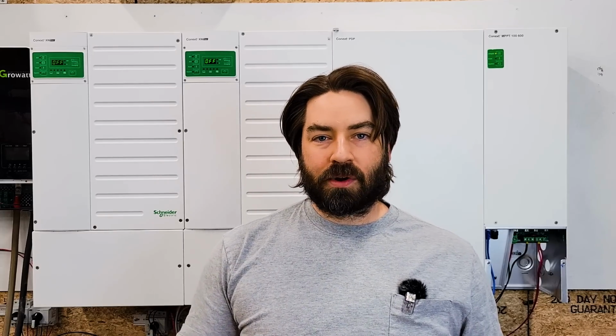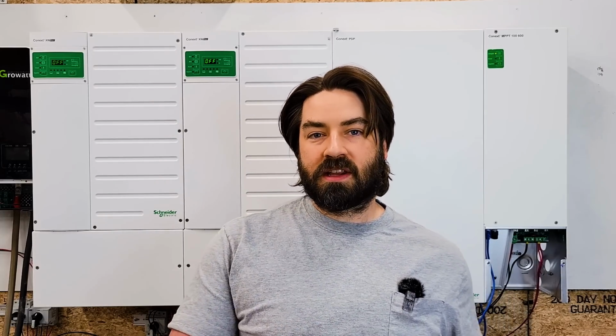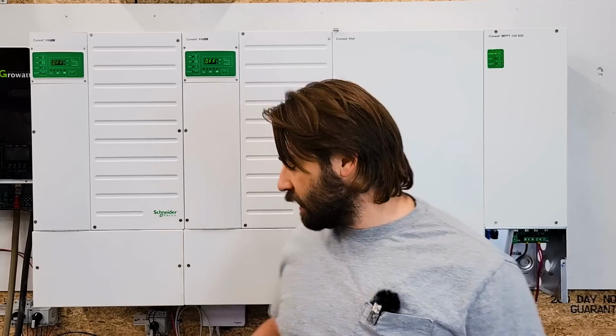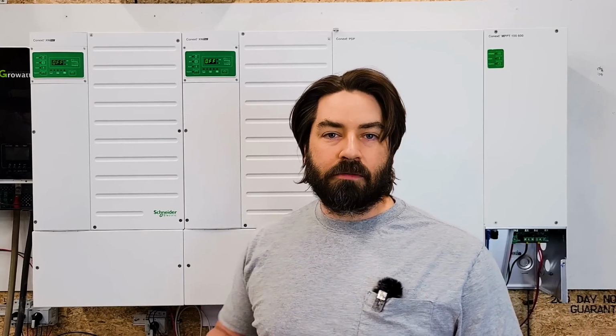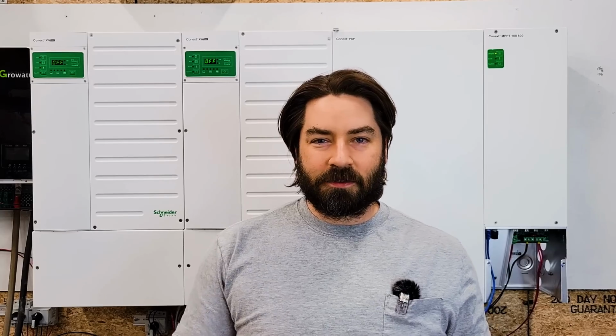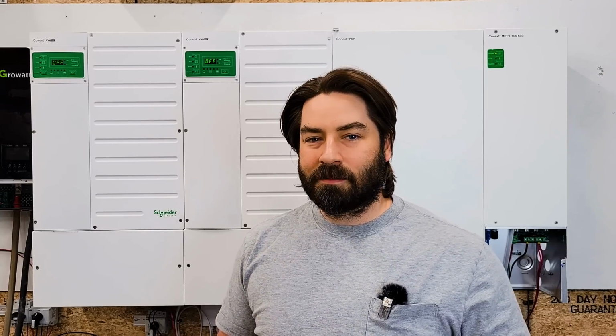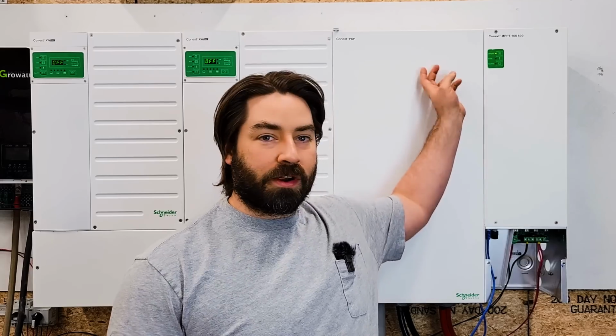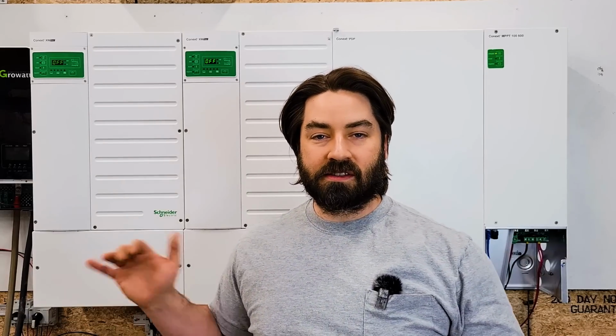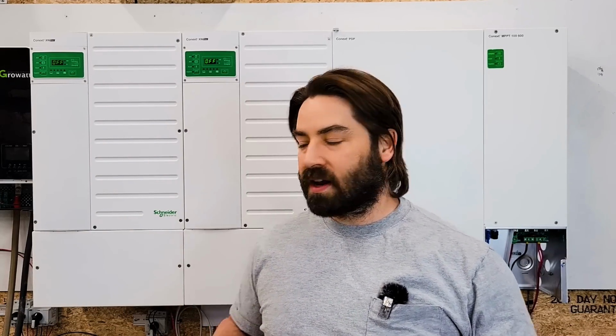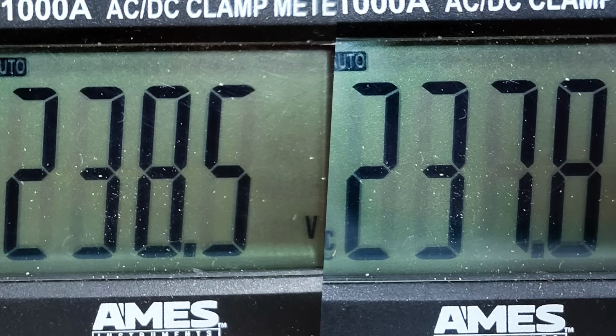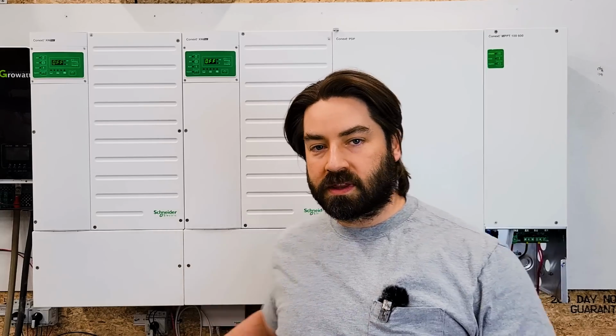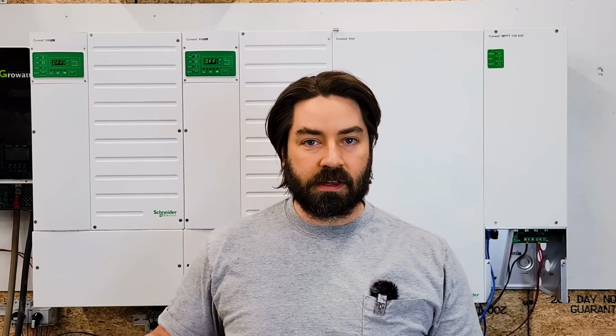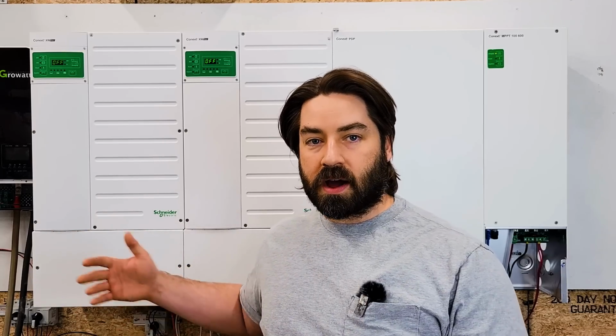So there is a calibration that you can do, and it used to be that you needed an extra tool, but Schneider, when they updated to the Insight Home, got rid of the need for that extra tool. So I'm going to give you the cliff notes on calibrating these inverters. Basically, they both need to be on, but the circuit breakers up here need to be off, so they're not actually tied together. I then use a multimeter and check the voltage right at the output terminals on both. And I noticed that they were just slightly off, about 0.8 volts from each other. And that was verified with the Insight Home, so the Insight Home was reading accurately as to what the voltage was. And I checked that with my multimeter.